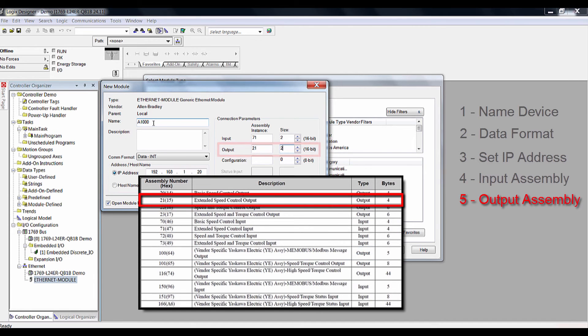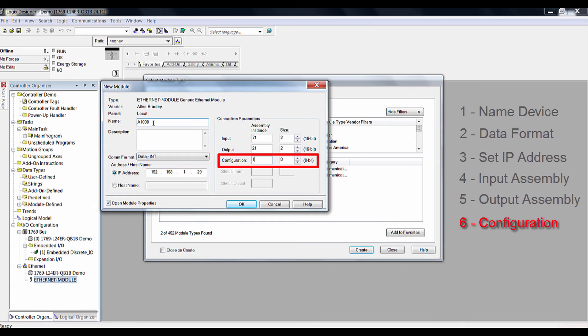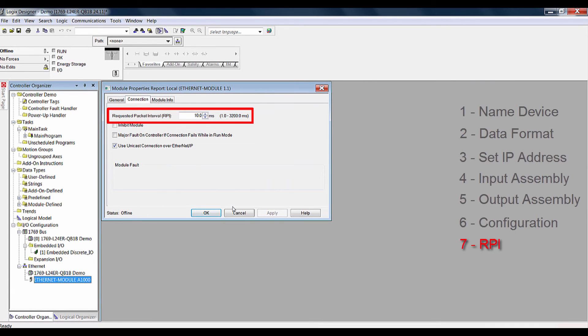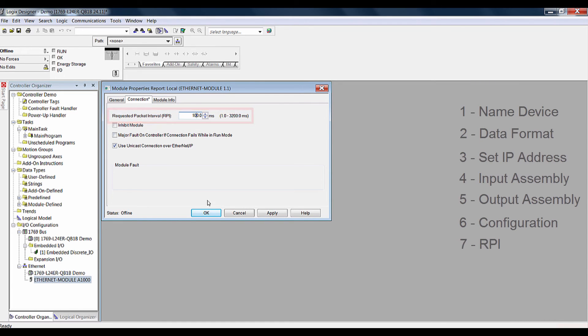Step 6 is to simply set the configuration number to 1 and then click OK. The seventh and final step will involve changing the RPI or requested packet interval time. It is recommended to use 100 milliseconds to reduce the amount of processing required from the PLC.